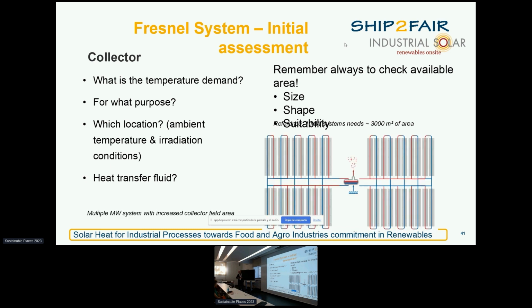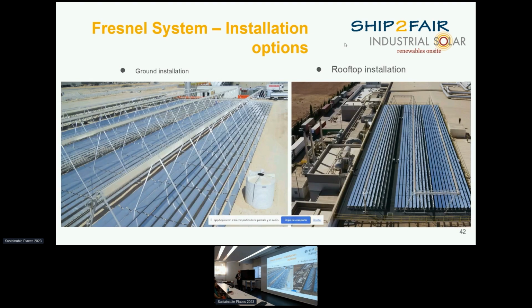It's a modular system that you basically connect in rows with the hydraulic control system to a steam drum that then is integrating and generating steam in this example. Installation options are basically two. The ground installation, where you can see here the systems are put on the ground, on concrete roots, feet, and also rooftop installation. This case here was made, interestingly, with the BOP, what you call the balance of plant, installed on top of the boiler room, and the steam drum, which is what you see, this big vessel here, is delivering steam to the main steam grid here, which is actually below where you see the chimneys here. The boilers are installed underneath.